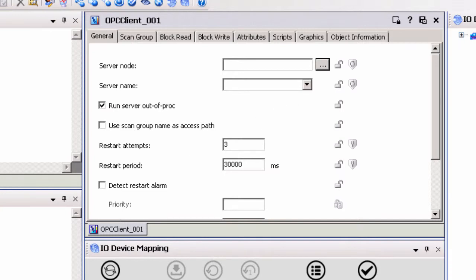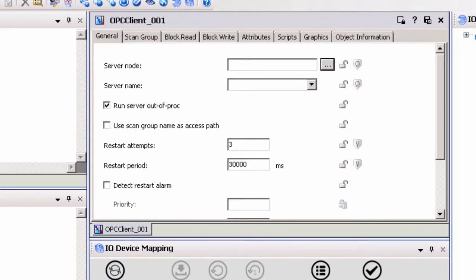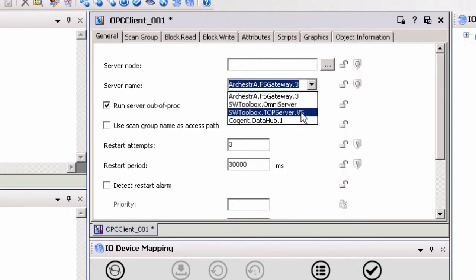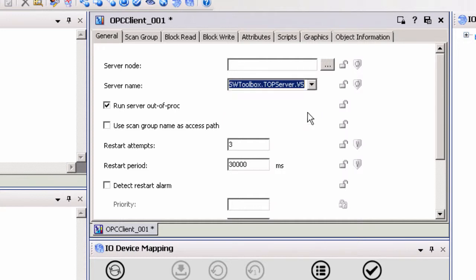If a remote OPC connection is being made from System Platform to TopServer, Windows DCOM security will play a factor in the success of your connection. If this is the case, please refer to our DCOM tutorial guide available at softwaretoolbox.com/DCOM. Once the server node is selected, you will be able to browse for the available OPC servers by expanding the drop-down menu beside the server name field. Since we are connecting to TopServer, we will select swtoolbox.topserver.v5 from the list.